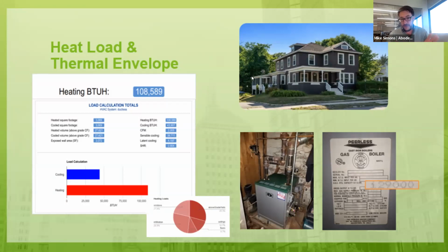When I was doing the Manual J heat load calculation, I put in my uninsulated walls, my single pane windows, my leaky attic, and it ended up putting out a number of my home needing 108,589 BTUs per hour. Then when I went down into my basement and looked at my steam heating system and what its output was, it was 129,000 BTUs per hour. So 129 is bigger than 108. My steam heating system was properly designed. It had enough heating capacity to surpass my heat load.